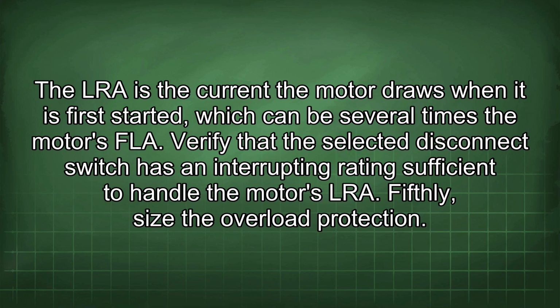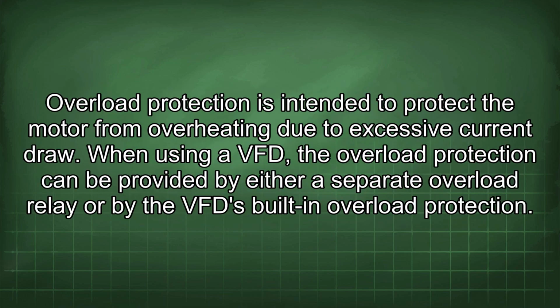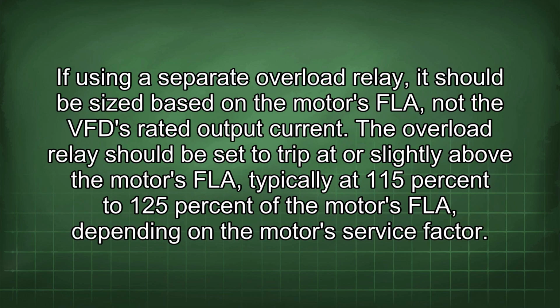Fifthly, size the overload protection. Overload protection is intended to protect the motor from overheating due to excessive current draw. When using a VFD, the overload protection can be provided by either a separate overload relay or by the VFD's built-in overload protection. If using a separate overload relay, it should be sized based on the motor's FLA, not the VFD rated output current. The overload relay should be set to trip at or slightly above the motor's FLA, typically at 115% to 125% of the motor's FLA, depending on the motor's service factor.